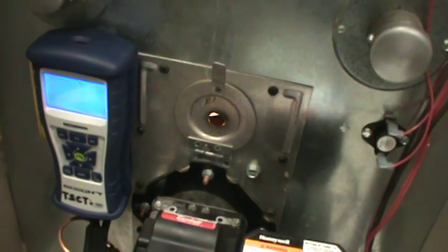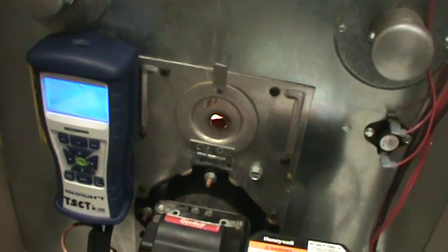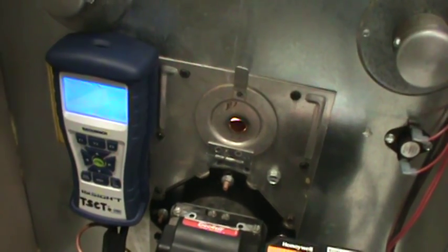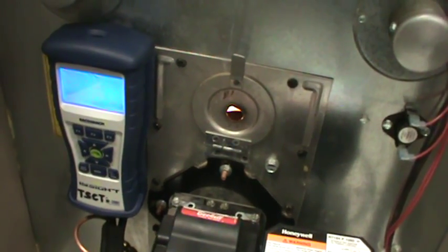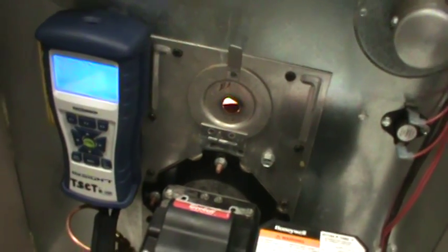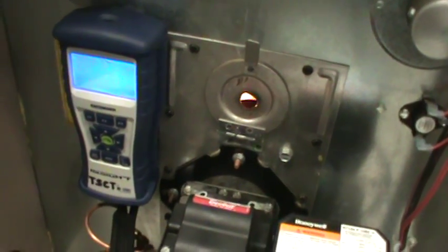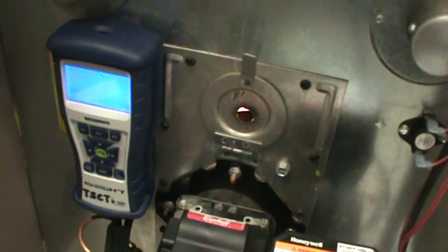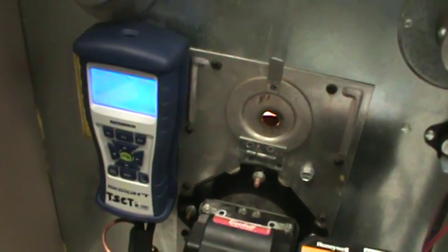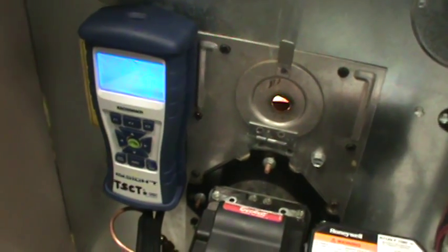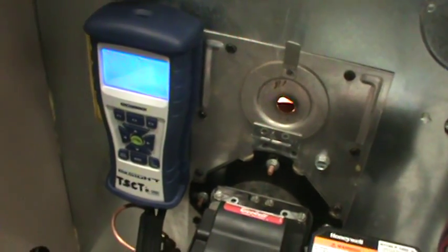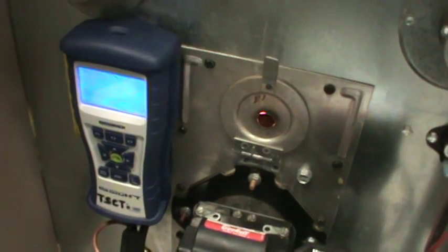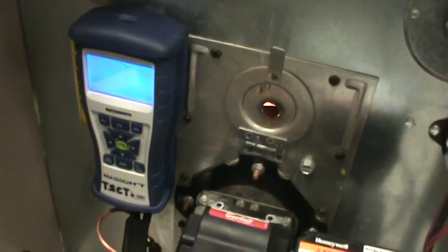This should be done in the beginning when you first fire up the unit. It's a lot easier to get a negative 0.02 in the wintertime. So I tell people, in the fall or spring, if you get a negative 0.01, you're probably going to be okay. But if you're getting a negative 0.01 and you can't get enough draft, you're probably not going to be good in the spring and the fall when you need a little bit of heat, because it's harder to get draft when it's warmer out than when it's colder out.